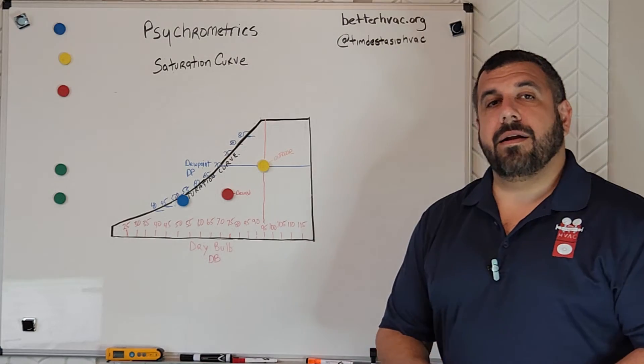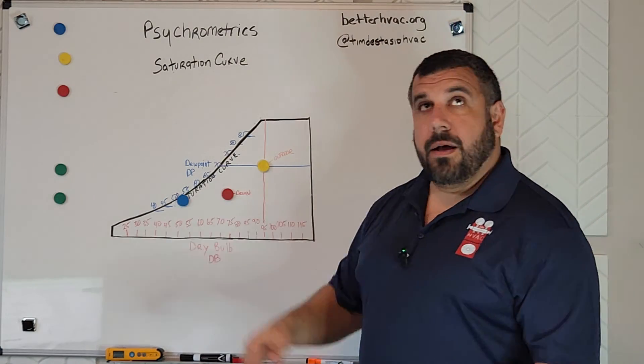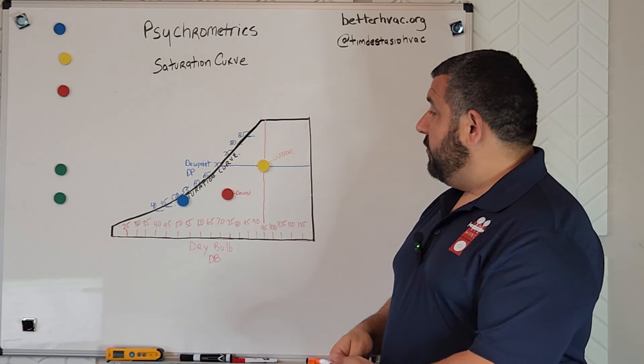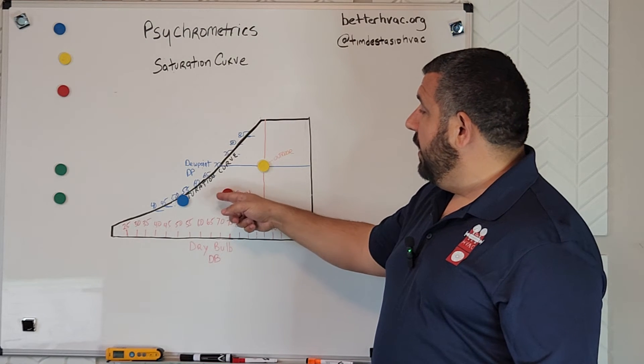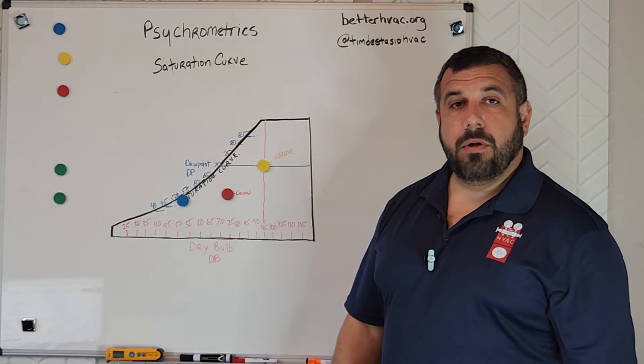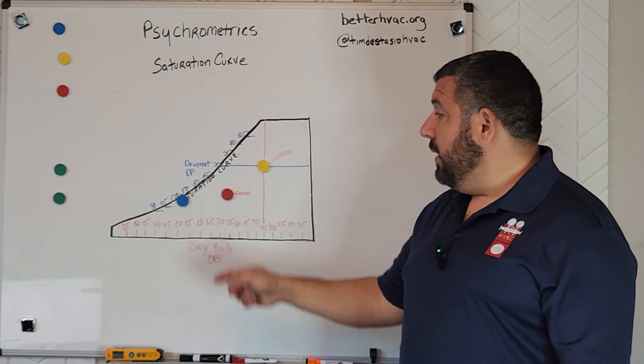And so this is really the supply air temperature. And that comes out of our supply registers. It mixes in with the room and it sort of keeps this dot where it is, because if it wasn't there, then our outdoor conditions would just pull our dot back up towards being hot and humid.